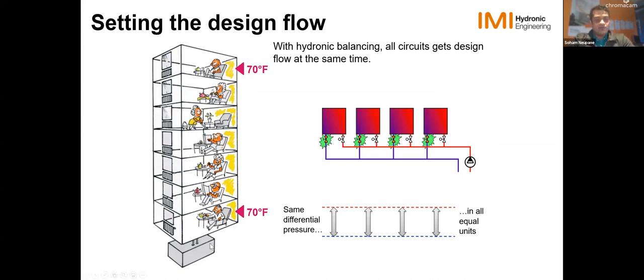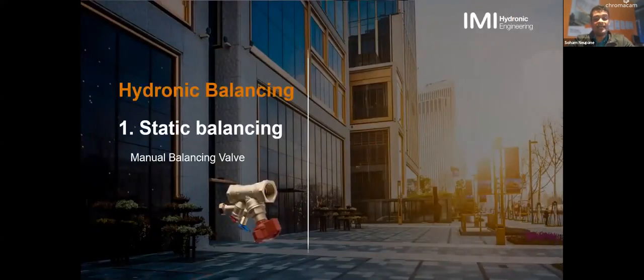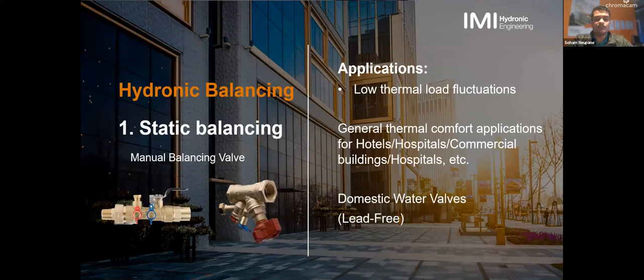So what are different ways of balancing, right? So let's look into that. So there are two widely used ways for balancing. And the first one we're going to look at is static balancing, which is also known as balancing with manual balancing valve, right? So this kind of balancing solution is ideal for low thermal load fluctuations, where you're not going to see high changes in the thermal load at all times. And it's also great for any general thermal comfort application for your hotels, hospital, commercial buildings, you name it.